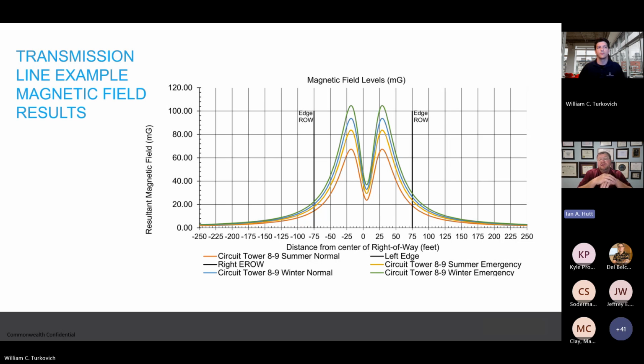And we can see impacts on peak magnetic field, where we're coming in at just over 100 milligauss for the worst case scenario winter emergency rating, which is not quite double, but near what it is for a summer normal rating. So that's interesting. We can also look at the edge of right of way. Just because of the structure and characteristics of the transmission line, we can see that we have a pretty good slope off once we get towards the edge of that right of way. Because this is a distance squared function, as you move away from the center line of the structure, our magnetic field levels drop considerably. We're hovering, best case scenario, around 17 milligauss, and worst case scenario, maybe around 21, 22.